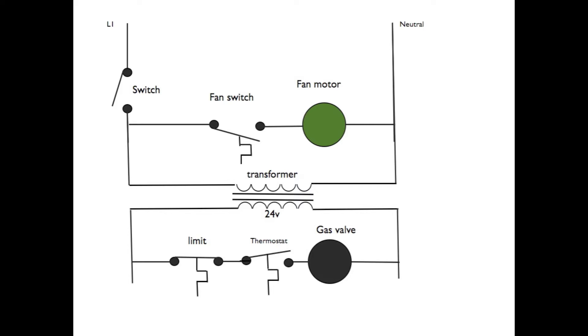We've got 120 volts in the upper part of the diagram, and then we've got a transformer that converts the 120 volts into 24 volts for the control circuit. So we've moved a lot of the controls down into the 24-volt circuit.